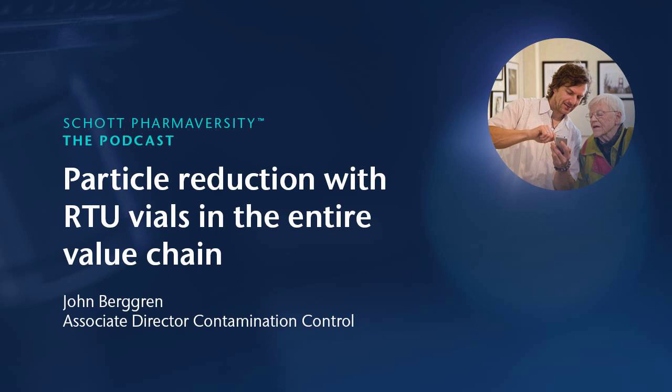Now, washing and depyrogenation also have an impact on glass. And these processes vary site to site, filling line to filling line. With Adaptic, the washing, the depyrogenation, the support utilities, the compressed air, and the water systems are all standardized. So every vial is run through the same process. At SCHOTT, we established a deep knowledge of our process through environmental monitoring and cleaning programs. And we can easily identify things that are happening because we pay a lot of attention to the product. It's easy to identify things like mechanical wear of belts or impacts of rails. Any particle that we identify can be traced back to its source.